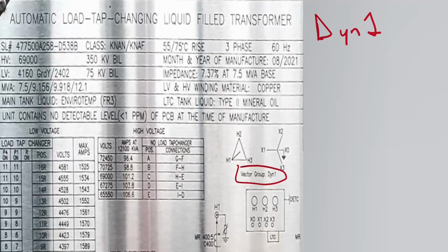Well, it gives us a voltage right here. That's our tap voltage. So make sure that you know what tap you're on. But this is the nominal. Nominal's typically going to be the middle tap, okay? Typically, not always, but most of the time it's going to be the middle tap. So this is a 69 kV on the delta, okay? And this on the secondary is a Y.